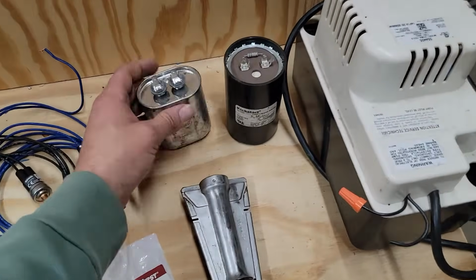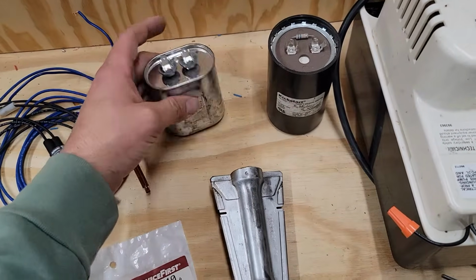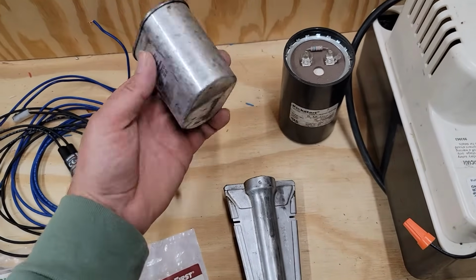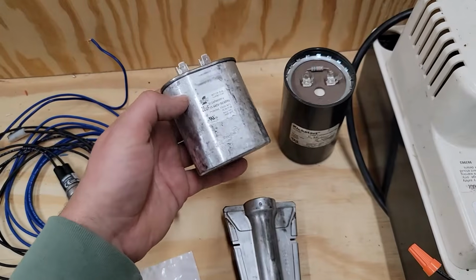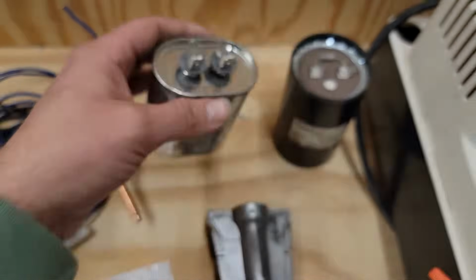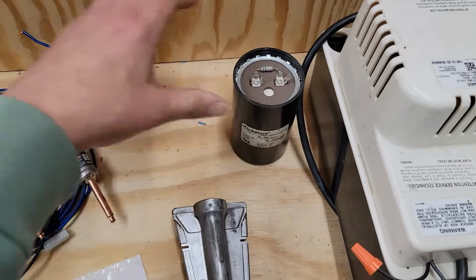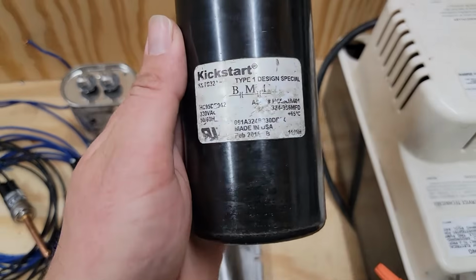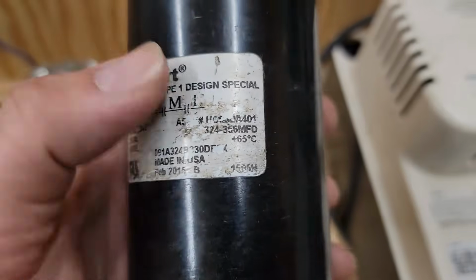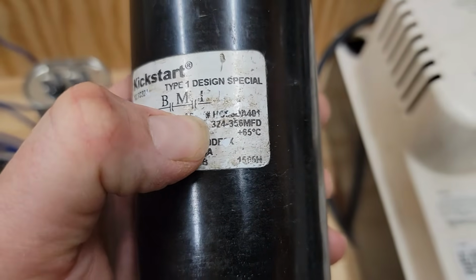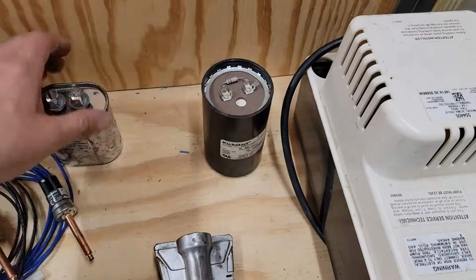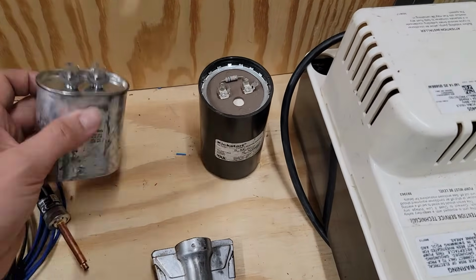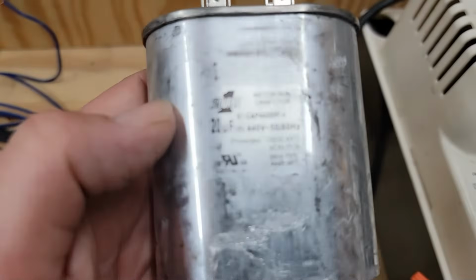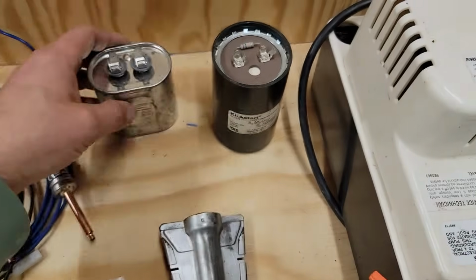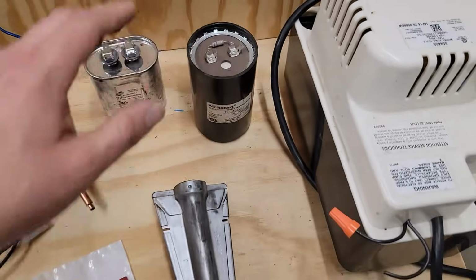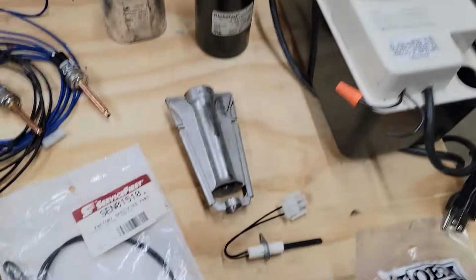All right, these are capacitors. This has a dielectric fluid and a piece of metal inside, basically, and it stores static electricity and it accumulates electricity so it can help motors run. This is a run capacitor, and this is a start capacitor. This start capacitor is rated for way more microfarads than that run capacitor. See, 324 microfarads. Typically, this is used to start the compressor, and this is used to run the compressor. So this right here is rated for 20 microfarads. This was rated for 300. So the difference is this is used to start, this is used to run.